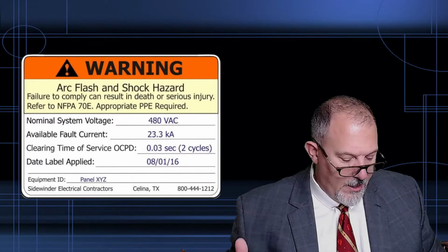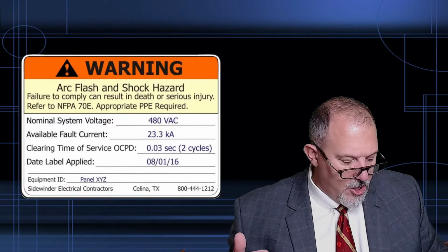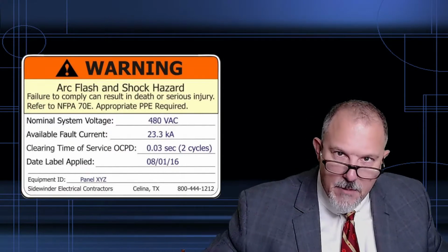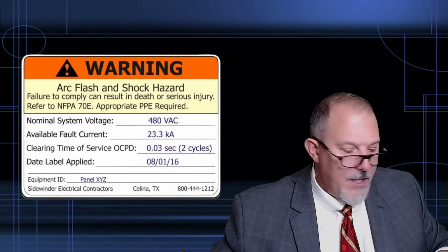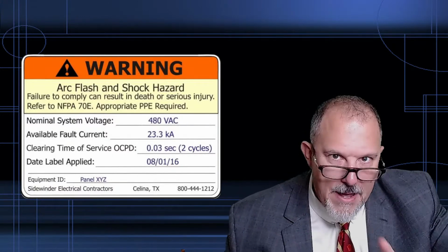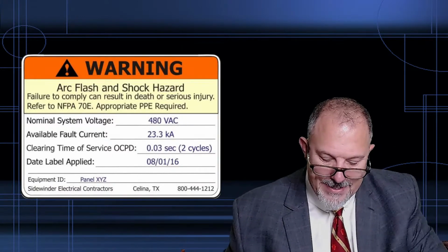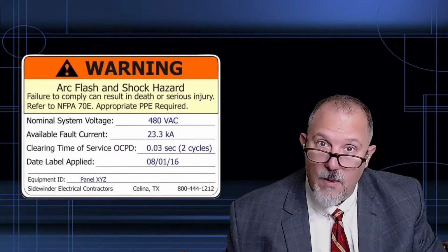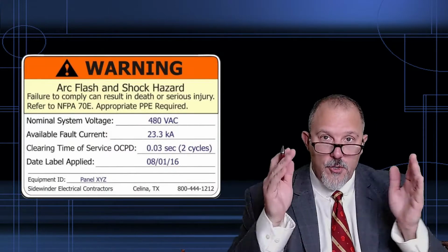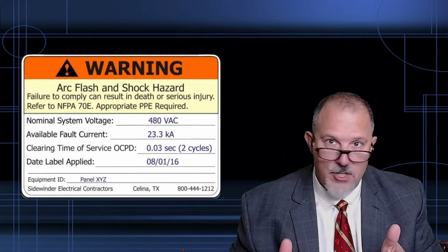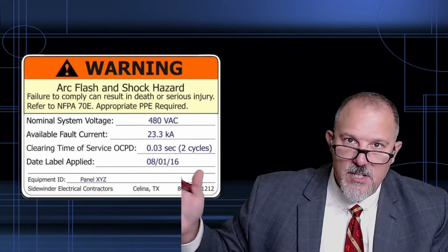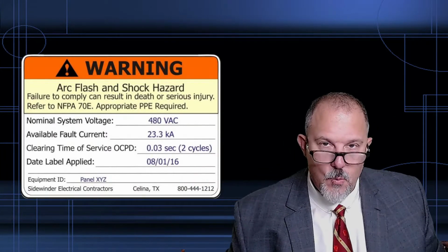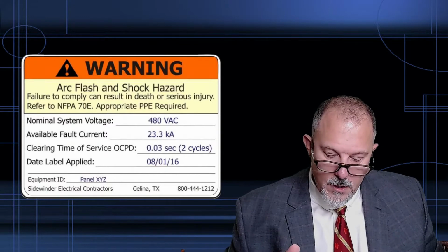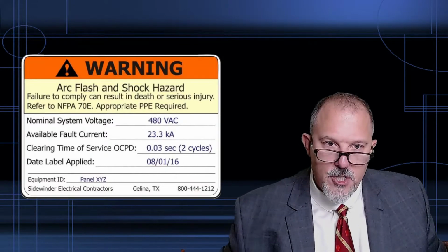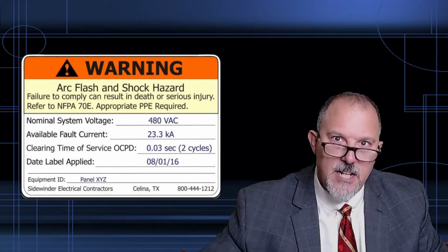110.24 is field marking. Service equipment at other than dwelling units should be legibly marked in the field with the maximum available fault current. 110.16 doesn't say maximum available fault current. It says available fault current. Why? Because when you're going to do an incident energy analysis, you're not worried about the maximum. Sometimes the minimum will give you the higher incident energy. So they had that discussion at panel 1.